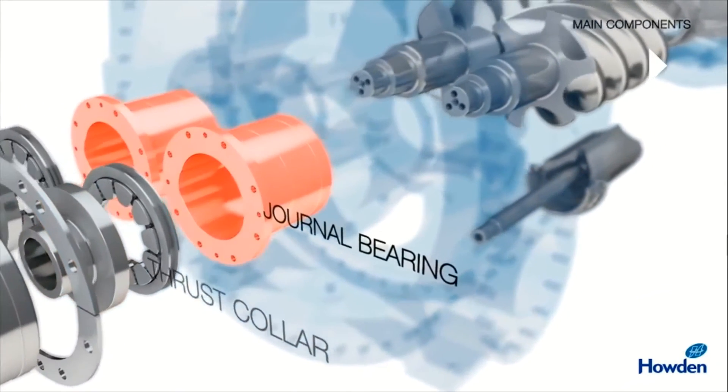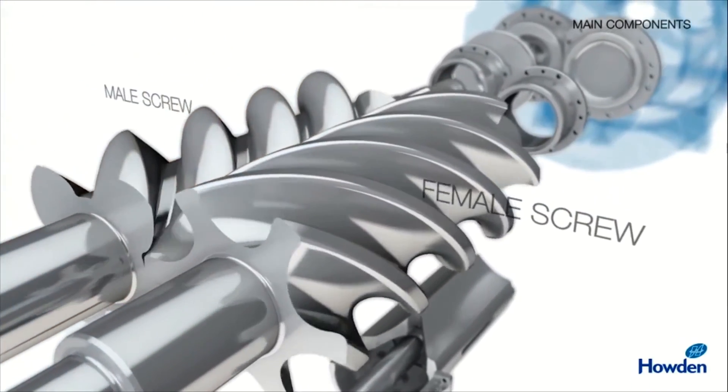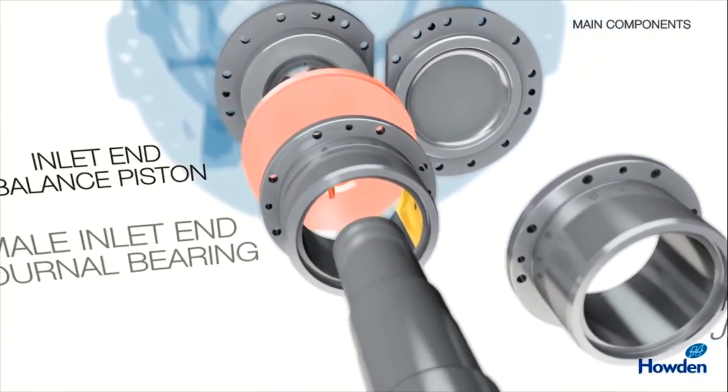Now you can see thrust collars which are provided in the bearings. Here you can see a female screw and a male screw — female inlet end journal bearing, and male inlet end journal bearing. Axial thrust which occurs on the shaft due to the high pressure developed by the screws is taken care of by thrust bearings. Thrust bearings are generally white metal — thrust pads are fixed to take the axial load of the rotors. A balancing piston of thrust is also inbuilt in the compressor.